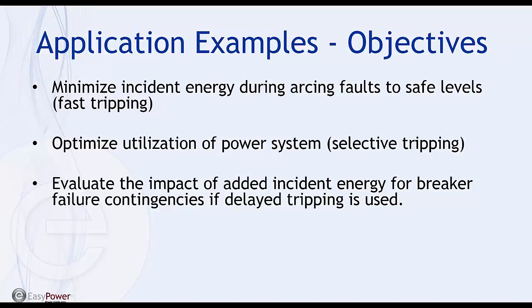And then safety is certainly a big issue. The first one is about safety and damage, but evaluating the incident energy for breaker failure is also very important, and that contingency needs to be looked at. Even though arc flash protection is very fast, you can't always rely on the breaker. So you have to ask yourself, if we put a 100 millisecond delay in there, or one of the other choices that you have on the dip switch, how much is your arcing current, and how much incident energy are you going to add to the system? So that always has to be a consideration.